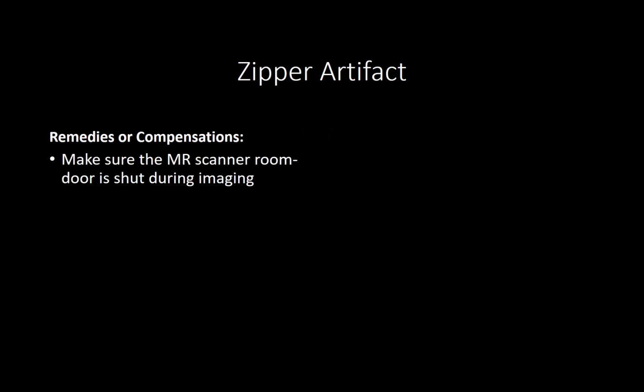Remedies or compensations for zipper artifact. Make sure the MR scanner room door is shut during imaging. Some technologists like to go in the room to grab certain equipment or IV materials. Try and prevent that while you're imaging to prevent this artifact.